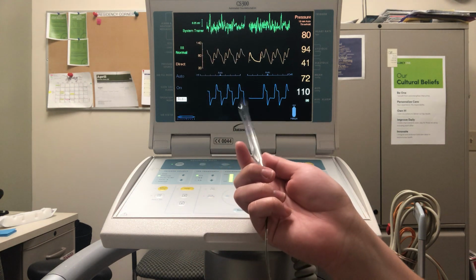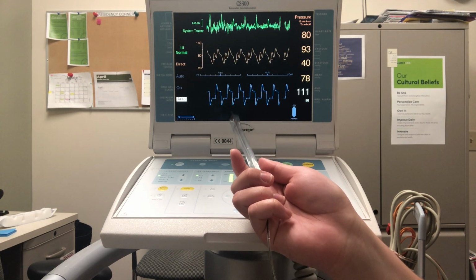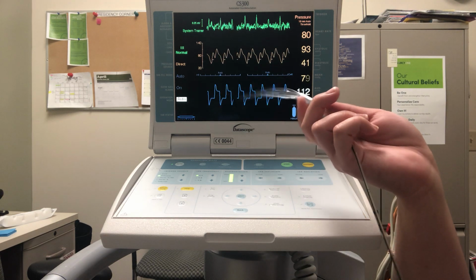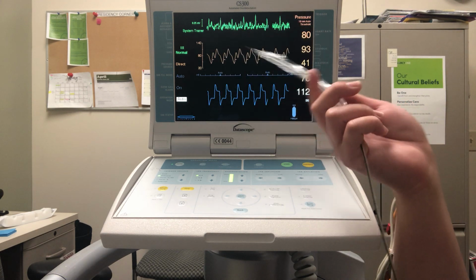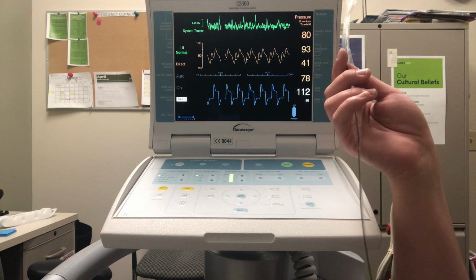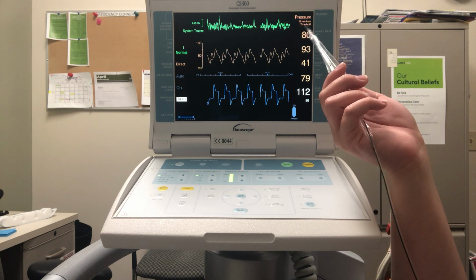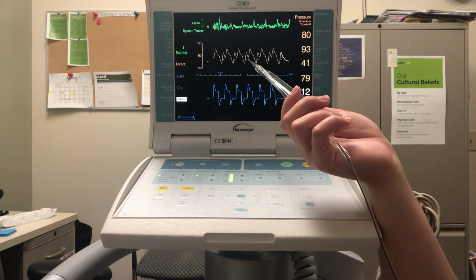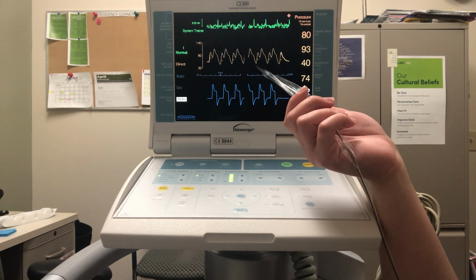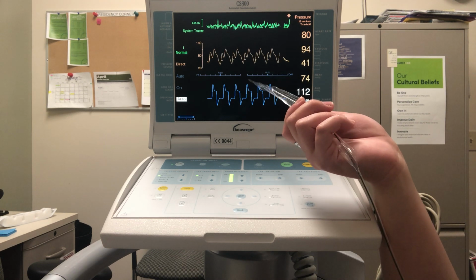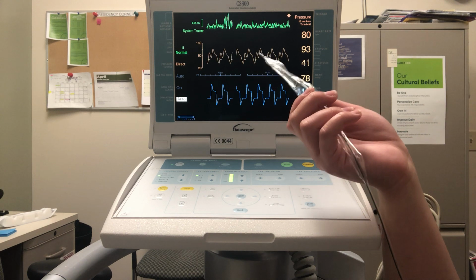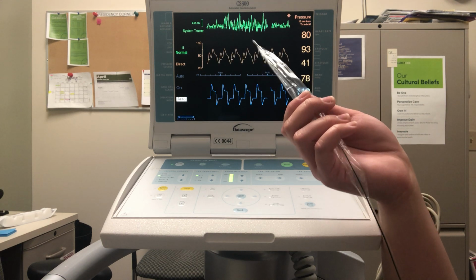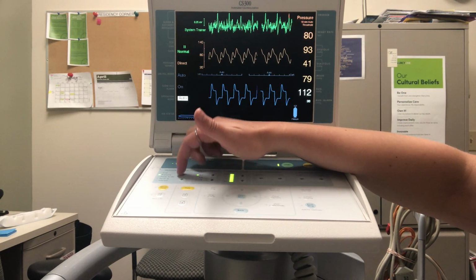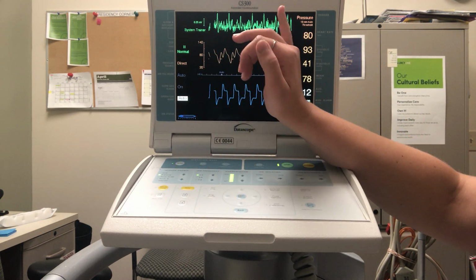We have a great waveform. And the reason for that is because the EKG was all messy and noisy, your balloon pump automatically diverted to going off a trigger from pressure, from the blood pressure. So now that it's triggering on pressure, it's working great. So the balloon pump will do that. Like I said when we were talking previously about the trigger source, this is the only time that it will do it automatically, is when, for whatever reason, your EKG cannot be read.